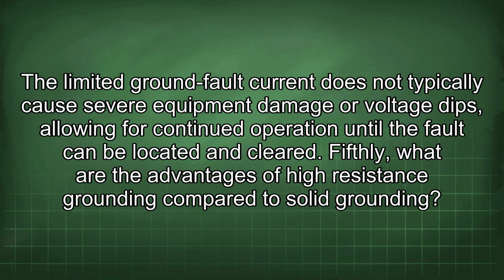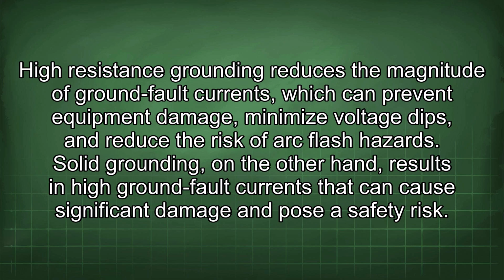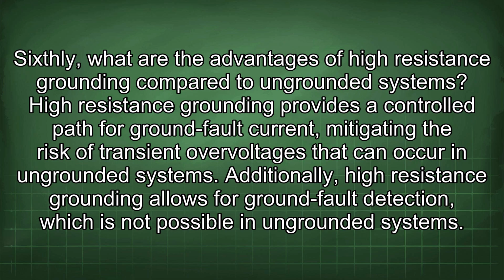Fifthly, what are the advantages of high resistance grounding compared to solid grounding? High resistance grounding reduces the magnitude of ground fault currents, which can prevent equipment damage, minimize voltage dips, and reduce the risk of arc flash hazards. Solid grounding, on the other hand, results in high ground fault currents that can cause significant damage and pose a safety risk. Sixthly, what are the advantages of high resistance grounding compared to ungrounded systems? High resistance grounding provides a controlled path for ground fault current, mitigating the risk of transient overvoltages that can occur in ungrounded systems. Additionally, high resistance grounding allows for ground fault detection, which is not possible in ungrounded systems.